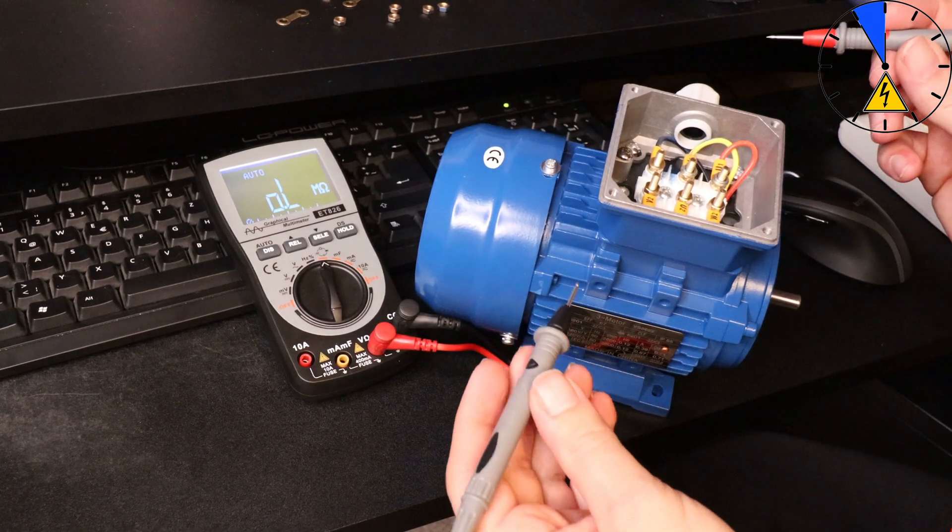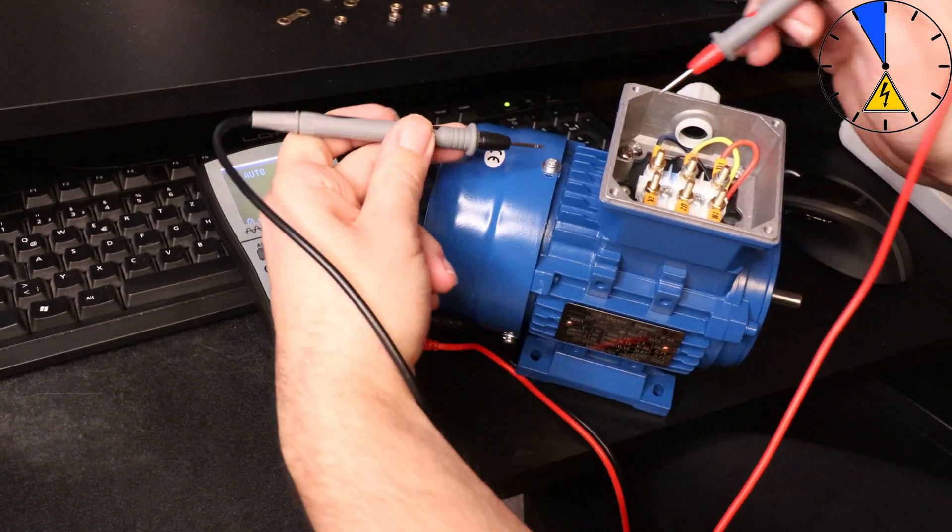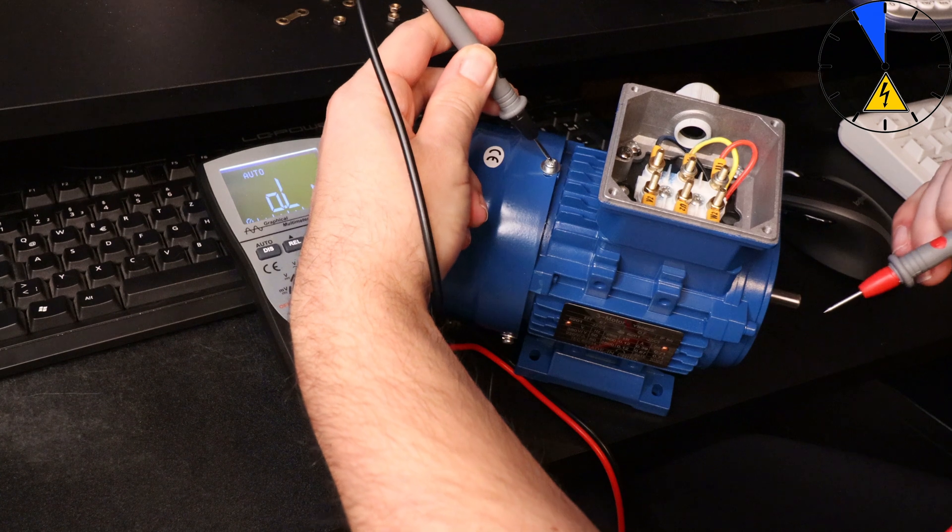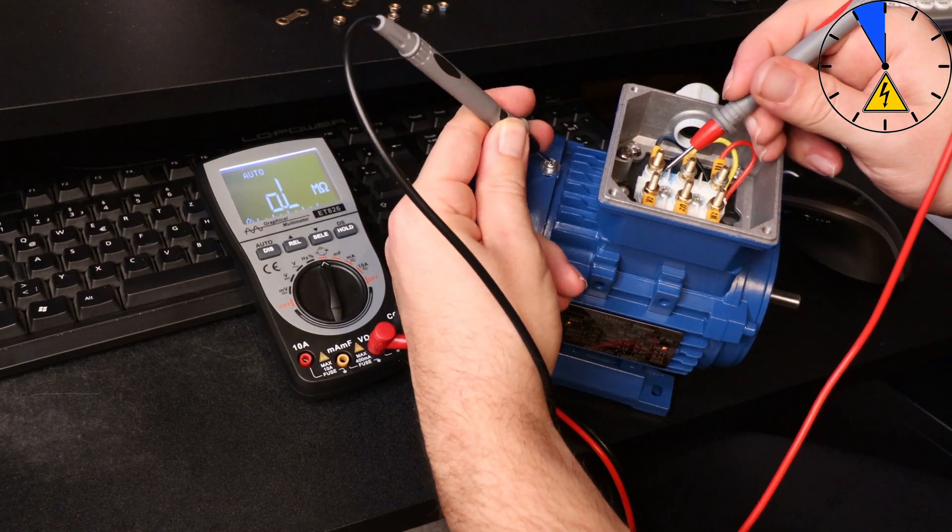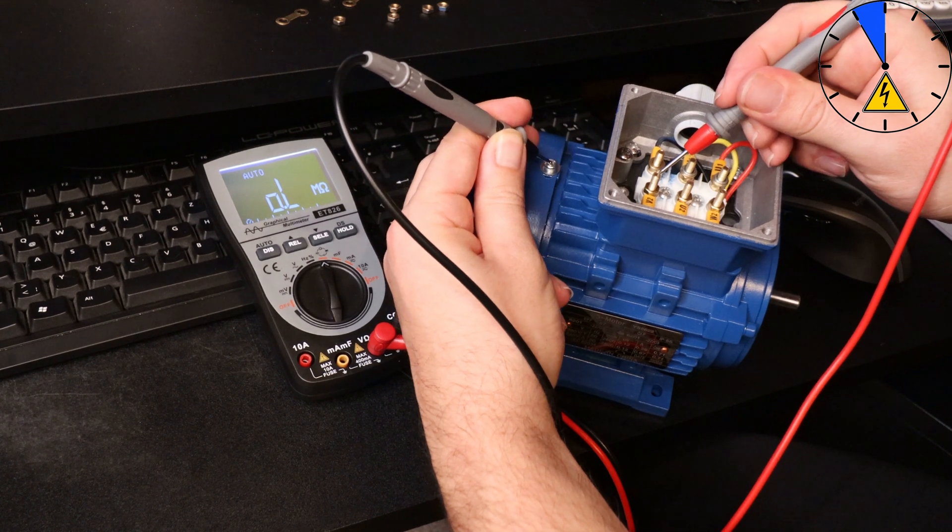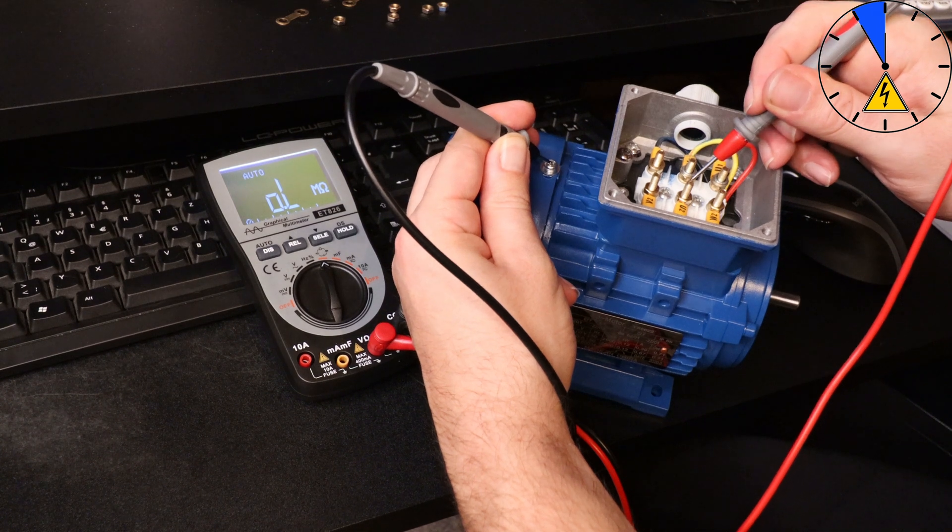The first test is the ground test. The ground test is between the body, for example here the screw of this body, and this connection of the motor coil, and the resistance must be infinite.